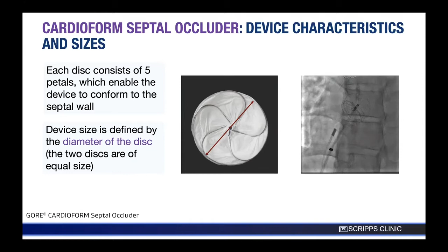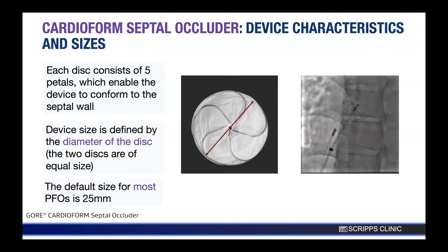In terms of device size, the Cardioform is defined by the diameter of the disc. Remember, the 2 discs are of equal size. So a 25 millimeter device has a disc diameter of 25 millimeters. The device sizes are 20, 25, and 30. Okay, so there's limited choices, but the default size for almost all PFOs, I'd say 80 to 90% of PFOs, will be 25 millimeters. Very straightforward. Again, unlike, for example, the AMPLATZER septal occluder, which is defined by the waist diameter, the size of the Cardioform septal occluder is defined by the disc diameter.